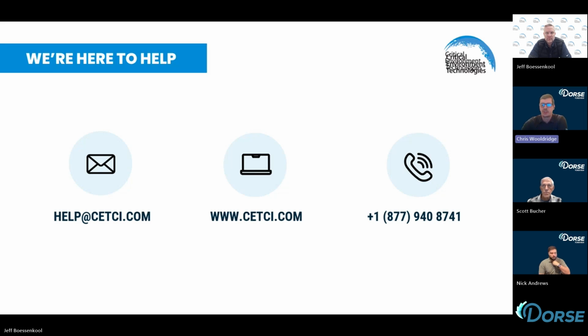We do have one question in the chat from Martin. How are A2L sensors calibrated, and are there issues getting R454B for testing? This came up on a California job recently. Yeah. So R454B, of course, is one of the common A2L gases that we've got sensors for. And I believe you can get standard calibration gas for the 454 gas. If you can't, let us know and we can help you source that.